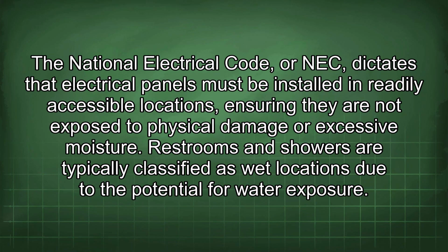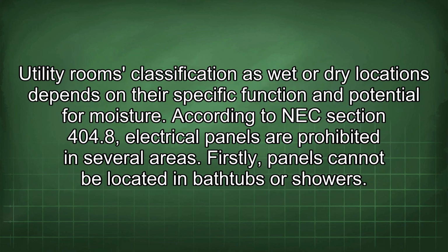The National Electrical Code, or NEC, dictates that electrical panels must be installed in readily accessible locations, ensuring they are not exposed to physical damage or excessive moisture. Restrooms and showers are typically classified as wet locations due to the potential for water exposure. Utility rooms' classification as wet or dry locations depends on their specific function and potential for moisture.